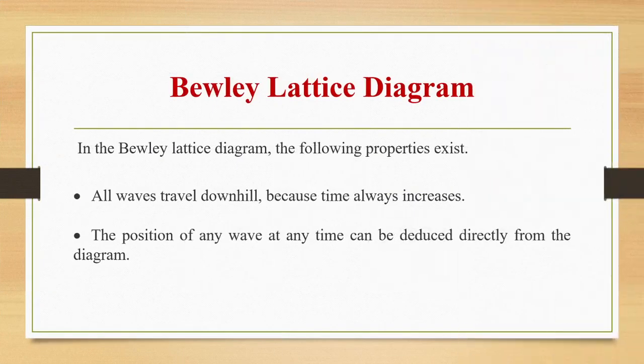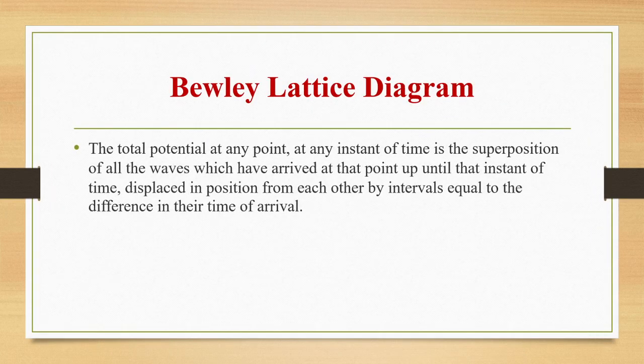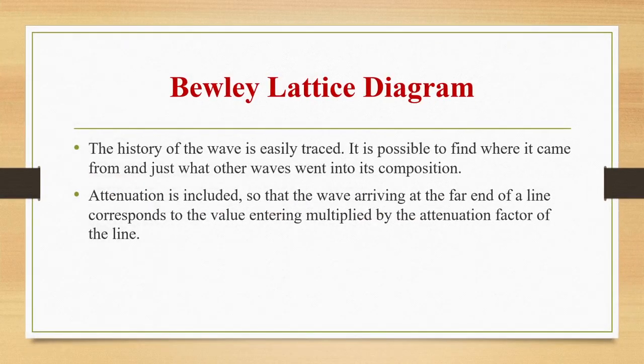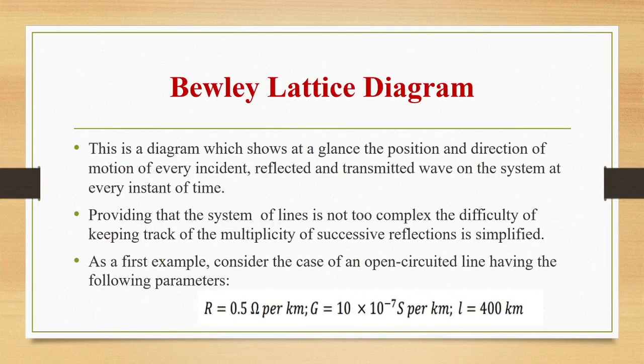In the Bewley lattice diagram, the following properties exist: (1) All waves travel downhill because time always increases. (2) The position of any wave at any time can be deduced directly from the diagram. (3) Total potential at any point at any instant of time is the superposition of all waves which have arrived at that point up to that instant, displaced by intervals equal to the difference in time of arrival. The history of the wave is easily traced. Attenuation is included so that the wave arriving at the far end of a line corresponds to the value entering multiplied by the attenuation factor.